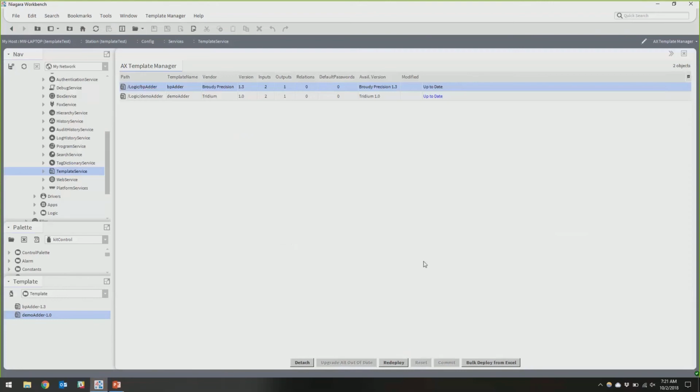A good example would be a VAV application. You could have all your box sizes, K factors, set points, and all. You add that configuration out in the template, then you can set all of those configuration values in your Excel file and just do a deploy, kind of like Johnson does with their XML files for PCT. I thought they said that was 4.6, and it might be. Yeah, I know it's a feature that's used big time with the Edge stuff. So it would make sense that it's 4.6, not 4.4.